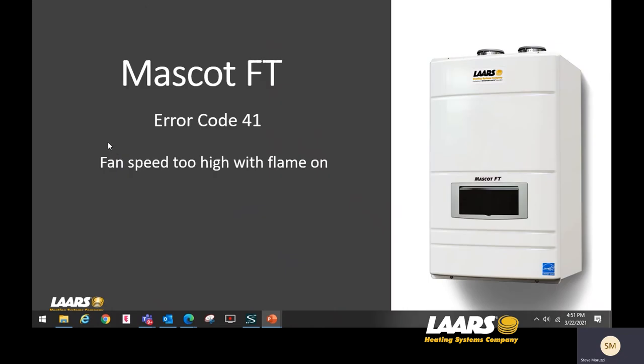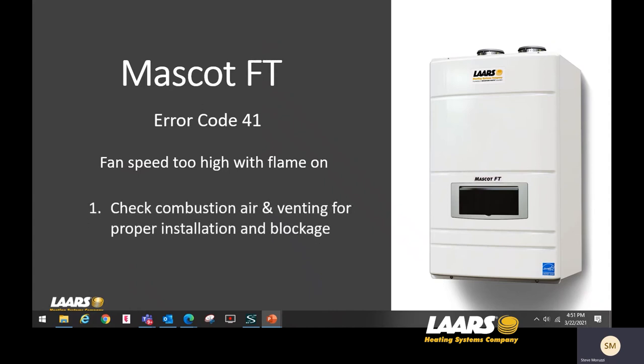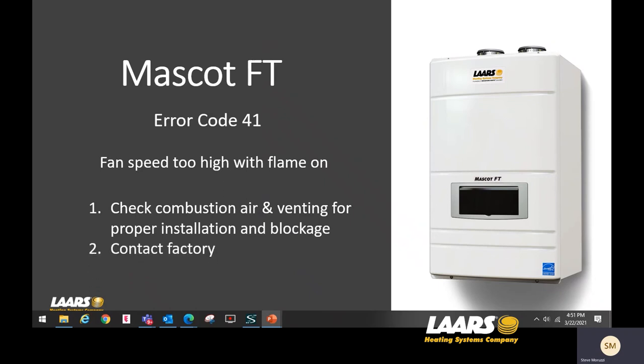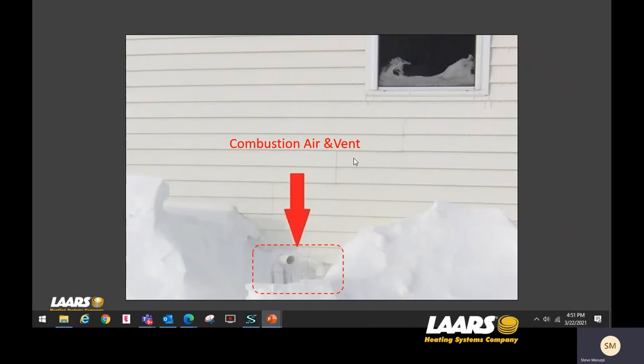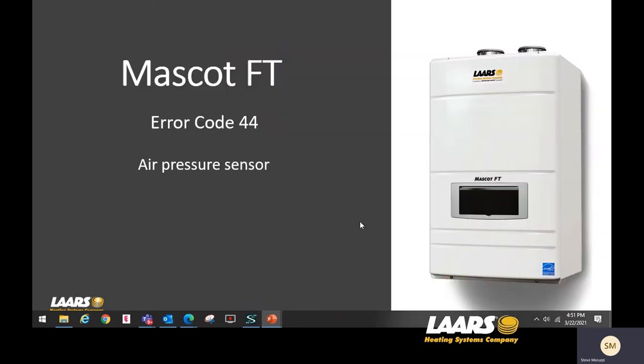Next, error code 41 — fan speed too high with the flame on. Check your combustion air and venting for proper installation or blockage. If everything checks out, contact the factory. Here's a perfect example: in a cold climate during a snowdrift or snowstorm, your combustion air and vent can get plugged and generate this error code.